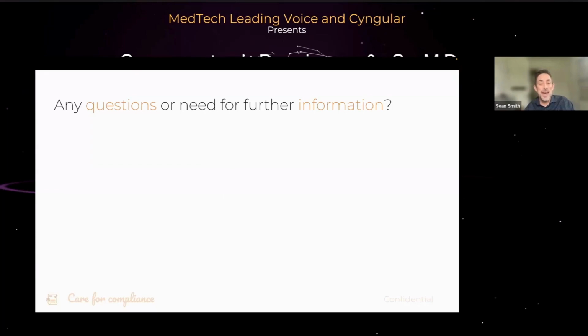So Petra, somebody asks, is a penetration test strictly necessary for software as a medical device, or are there any alternatives? I think at the end of the day, it ends up with your risk management process, right? And it would really depend on what your device is doing. I can imagine there are devices that are not going to be connected to the public internet, which are software as a medical device used in isolation. In that case, a penetration test may not be the type of testing that's most relevant after you release the product onto the market. I think you will have to have a very clear rationale to the FDA in explaining why you're not executing a pen test. But I'm sure that there are ways in specific situations where a rationale may be acceptable.